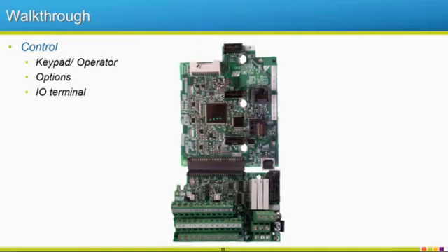Then we have our terminal board full of our inputs and our outputs, all of our digital, so our 1s and our 0s and our analog signals, so our 0 to 10 or 4 to 20 signals are all located on our terminal board down here. This terminal board is nice, it has non-volatile RAM, so if something was ever to happen to the rest of your drive but your terminal board was okay, you could just use your old terminal board in your new drive as long as certain things are kept the same, like it's the same engine size and control method and software revision.